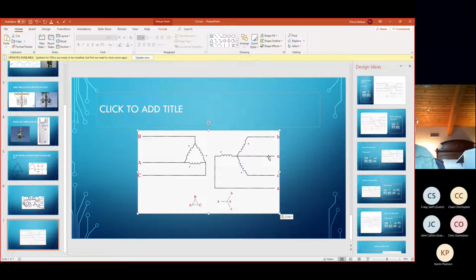I'll explain why in a second. And we want to see balanced impedance on the secondary of that transformer. Delta primary, Y secondary, with the center tap of the Y grounded. This is ideal. This is what you should see in new equipment installations. A lot of this other stuff that we see, the open delta included, is legacy stuff. It was done for cost savings reasons.